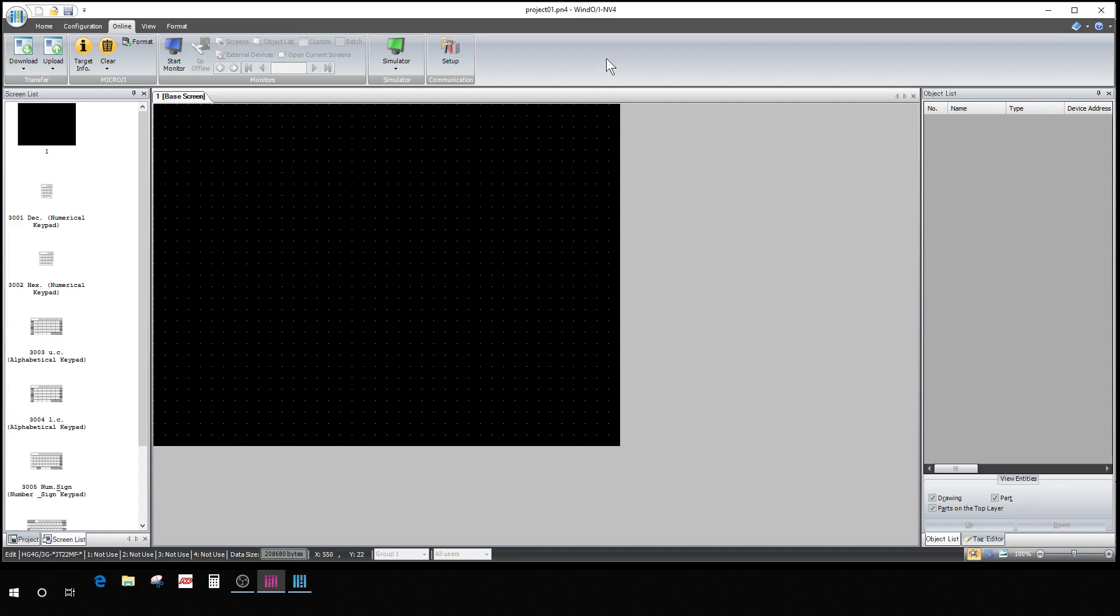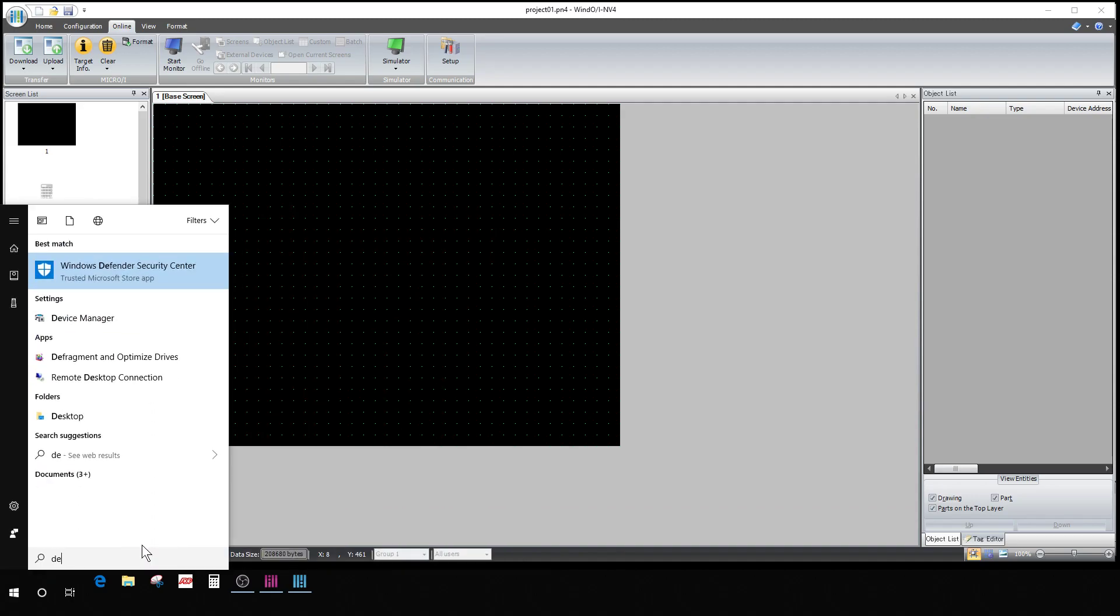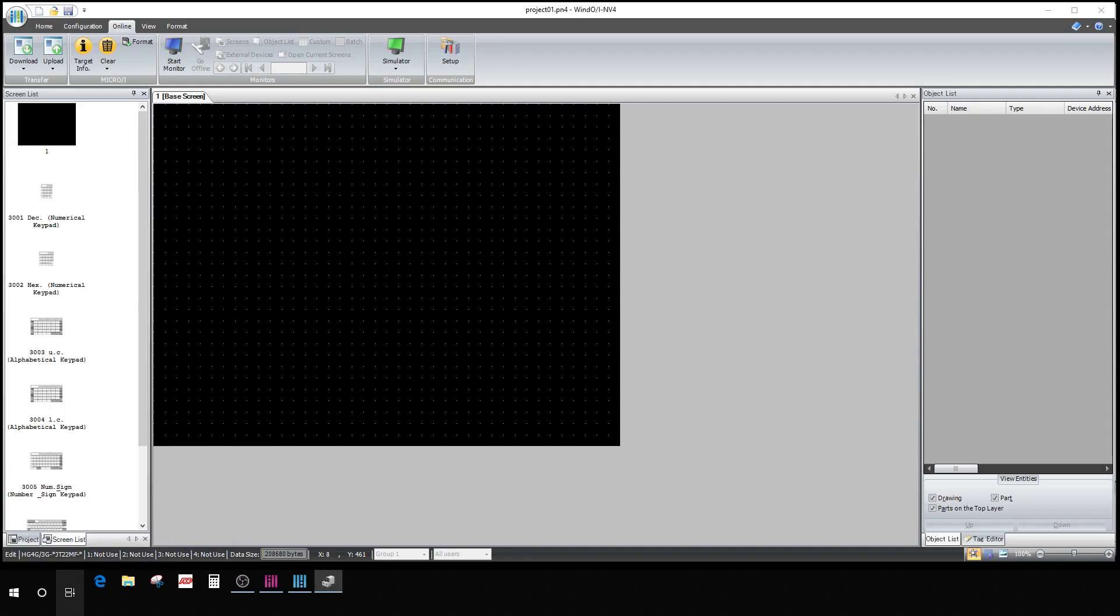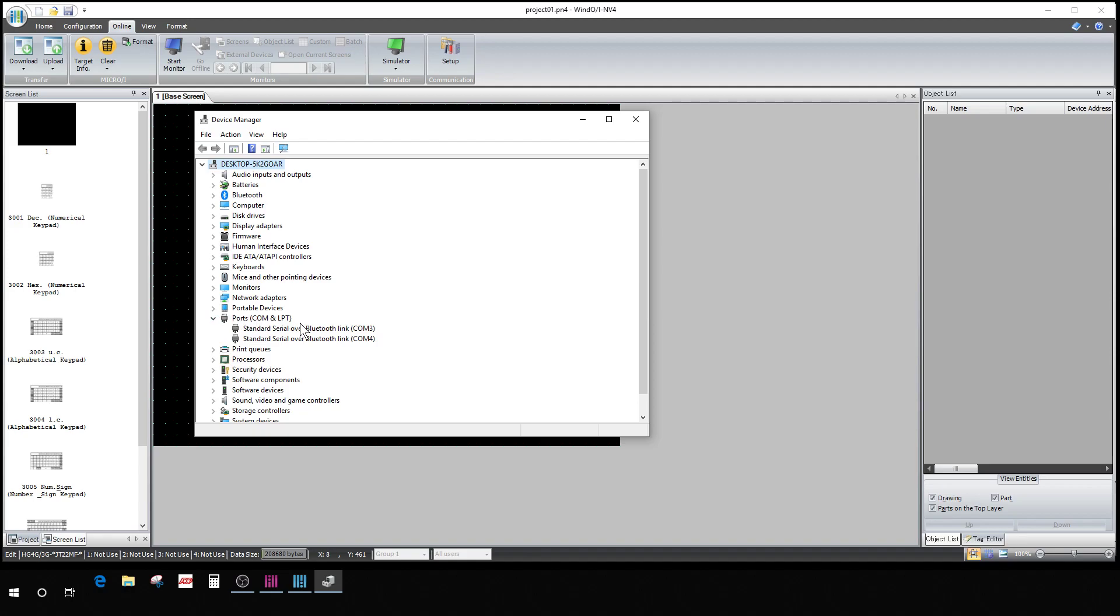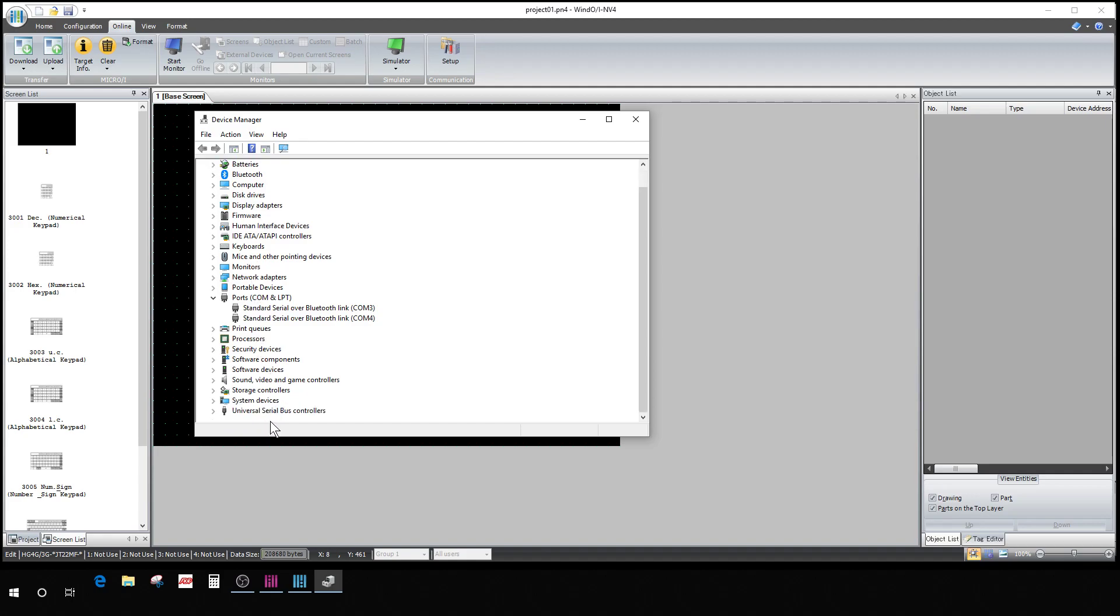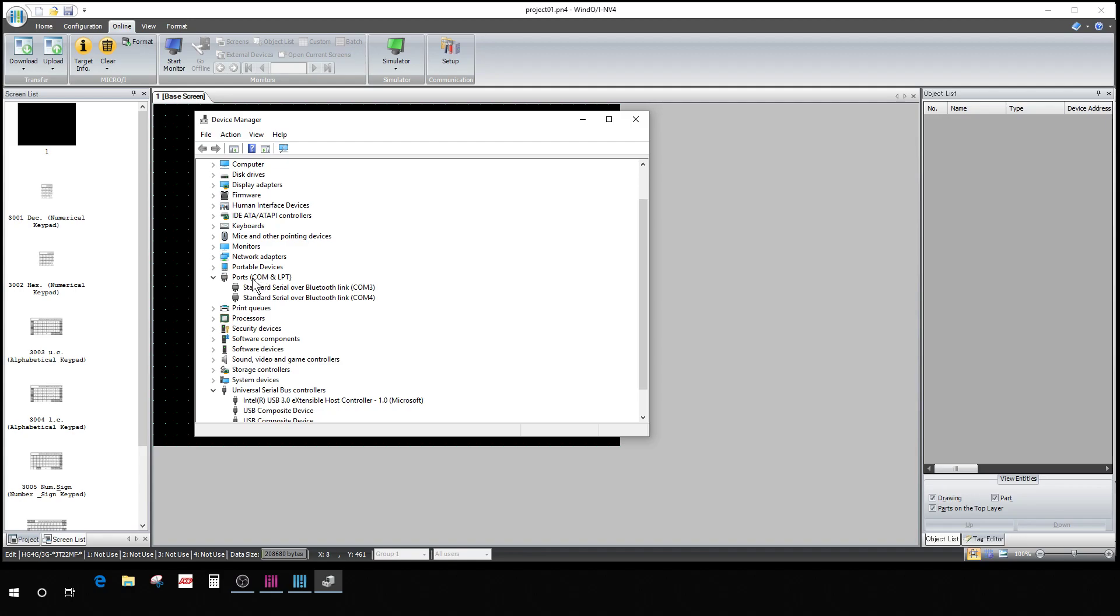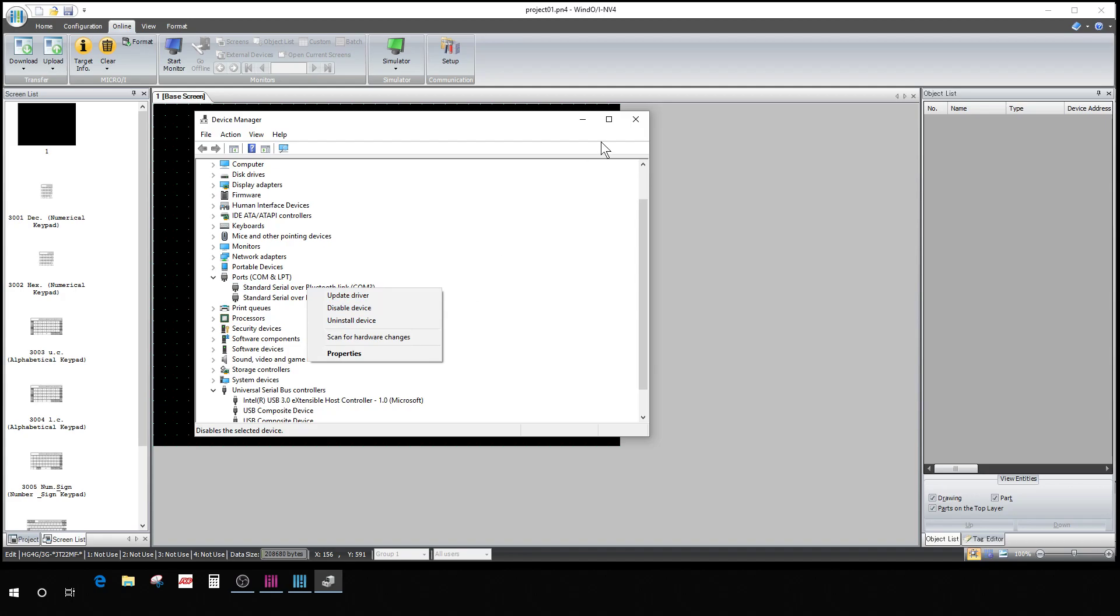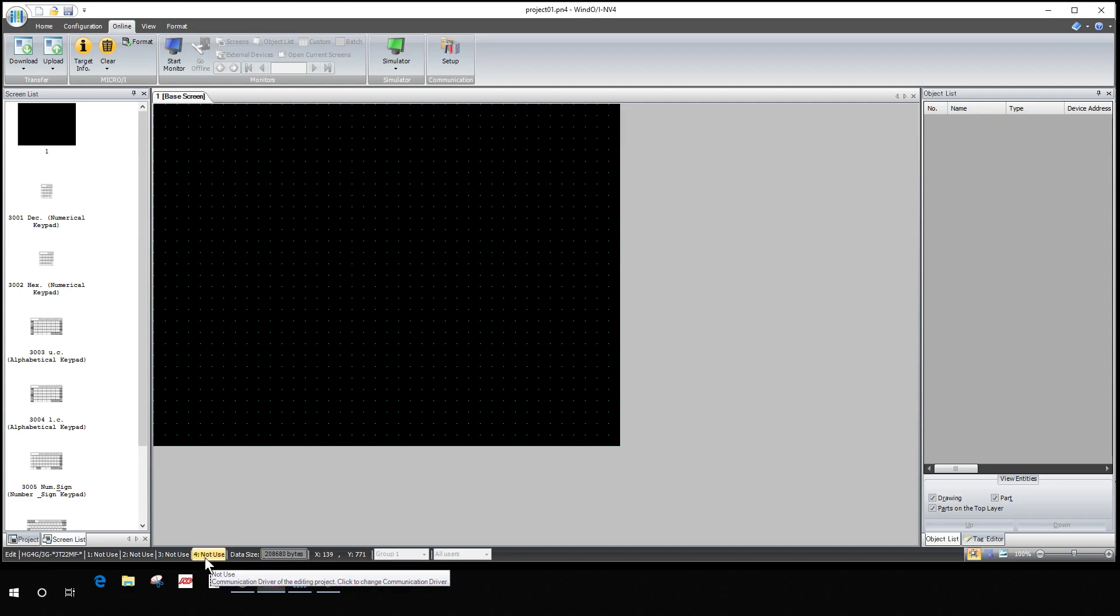One thing that I've noticed on my PC: if I'm having trouble with connecting I go to device manager. When I pull up device manager and come down to here, it's going to have your ports, might be under ports or under other devices. What my machine does sometimes, it'll actually marry that port to the PLC and it won't let me use it. So I have to physically come in here and right click it and go uninstall device, plug the USB back in so it sees it again, and then it'll communicate.